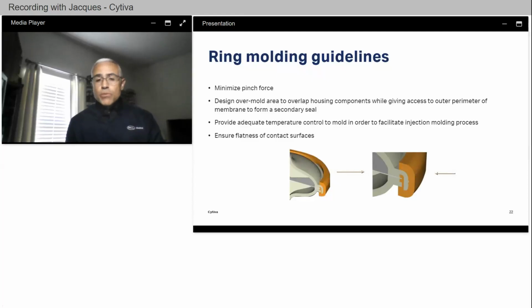Some general guidelines for ring molding include minimizing the pinch force applied to the filter material to prevent damage of its pore structure. Avoid venting hot gases from the process through the filter material to reduce the risk of damaging the membrane during the sealing process.